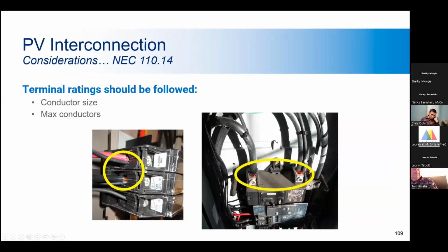Another potential problem that we see is terminal ratings need to be followed. Terminal lugs where you land wires are rated for conductor size and max number of conductors. So here we see a main breaker where conductors have been doubled up on terminals rated for a single conductor. In this case, we need to check the ratings on the terminals to ensure they're rated for 2 conductors. You can see that here and here. And on the left is the circuit breaker. This is the main breaker conductors, and this is the circuit breaker conductors that have too many connections installed in them.